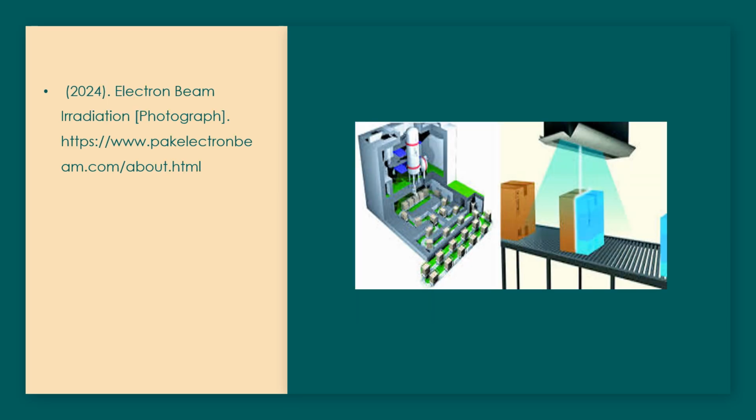Electron beam irradiation. This uses an accelerator that causes a beam of electrons. This beam is then used on packaged materials, such as packaged medical instruments, to kill microorganisms. The packaged material goes on through a conveyor belt and then is scanned by the accelerator.